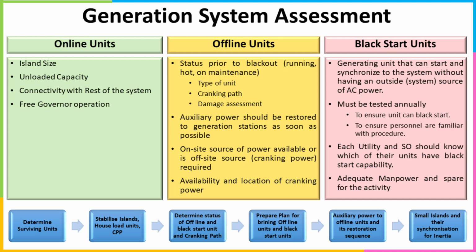Then the intention for the offline unit, as a system operator, should be that you provide at least the auxiliary power supply in a quicker manner, especially for a cold or hot start unit, so that the unit can be brought back. The auxiliary can run on the supply from the system. So that is the intent for the offline unit.